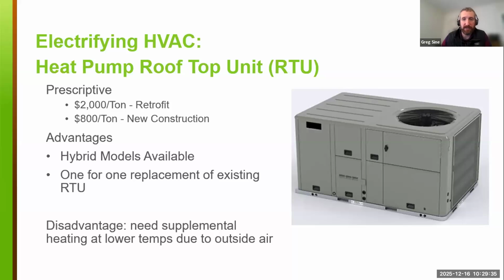One other technology we're seeing some success with, or seeing implementation with, are hybrid heat pump RTUs, which typically use natural gas for heating at lower ambient temperature conditions. That can ensure performance and comfort when it's really cold out. It can also be a strategy to electrify within what the electric capacity of the building can support. So that's one benefit of taking a hybrid approach: you can select equipment and a sequence of operations that wouldn't necessarily result in a net increase on the electrical demand on the building, if it would be very burdensome to make updates, or there's limited capacity available in the street. So hybrid RTUs could be a good fit for that type of situation.